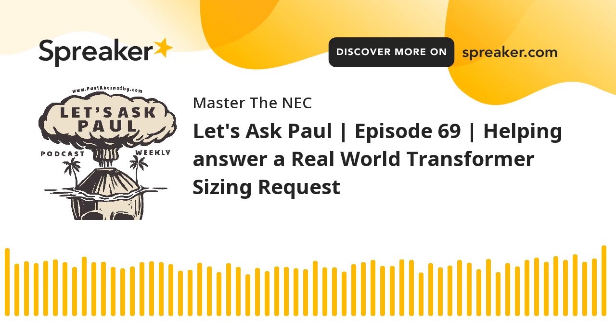So that breaker that's back in the 480 volt panel can serve as the overcurrent protection for the transformer, but it also can serve as the disconnecting means, provided you do the labeling back at the transformer. You get me? Okay. So that might save you a little money in how you want to run your installation.